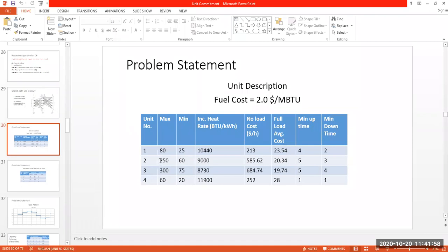So how do you choose? In this case, you simply apply the formula that I am going to mention. You take whatever value is possible from the first priority unit. Because the demand is higher than the maximum capacity of unit 3, you simply take 300 first. The remaining you can take from the next unit, because now you have unit 2 and 3 turned on.